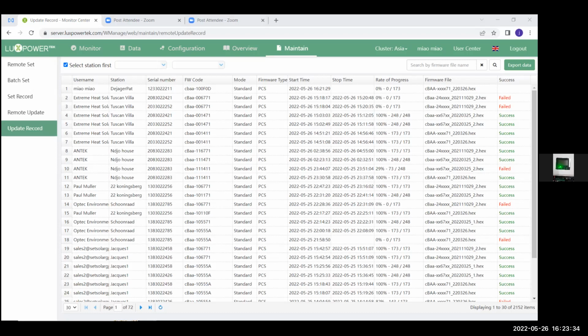That's what we are having a problem with on the monitoring side. If you have an internet connection that is fast but very unstable, it keeps on disconnecting from the server. So it's better to have a slower internet connection, but the stability of the connection is what is really important in this matter. We don't need a fast internet connection. We only need a stable internet connection. So if you have a 1 to 2 meg line that's stable, it will work perfectly without any trouble.